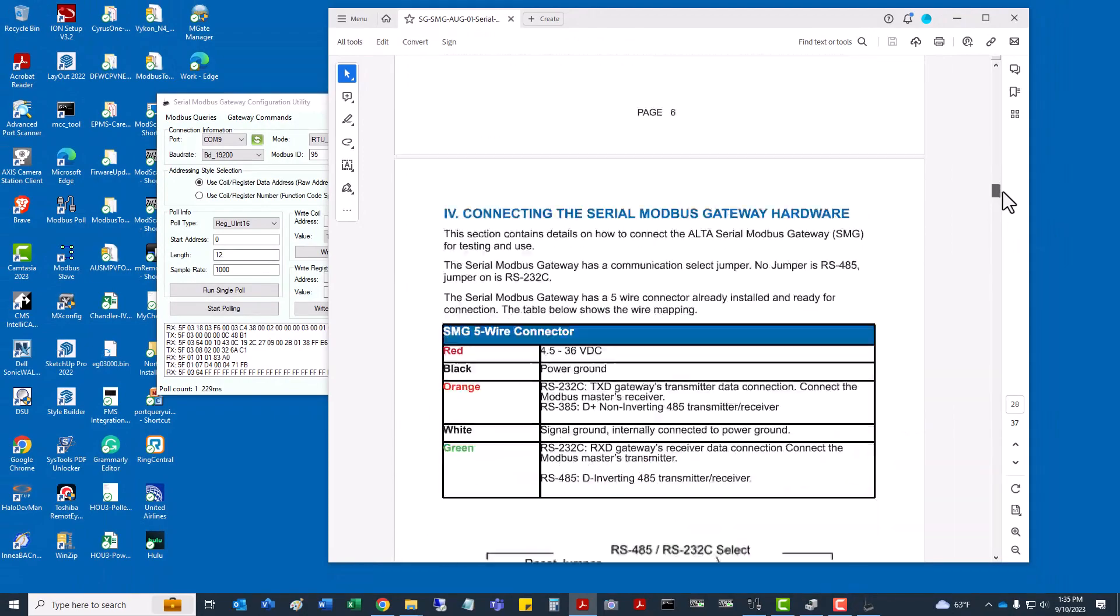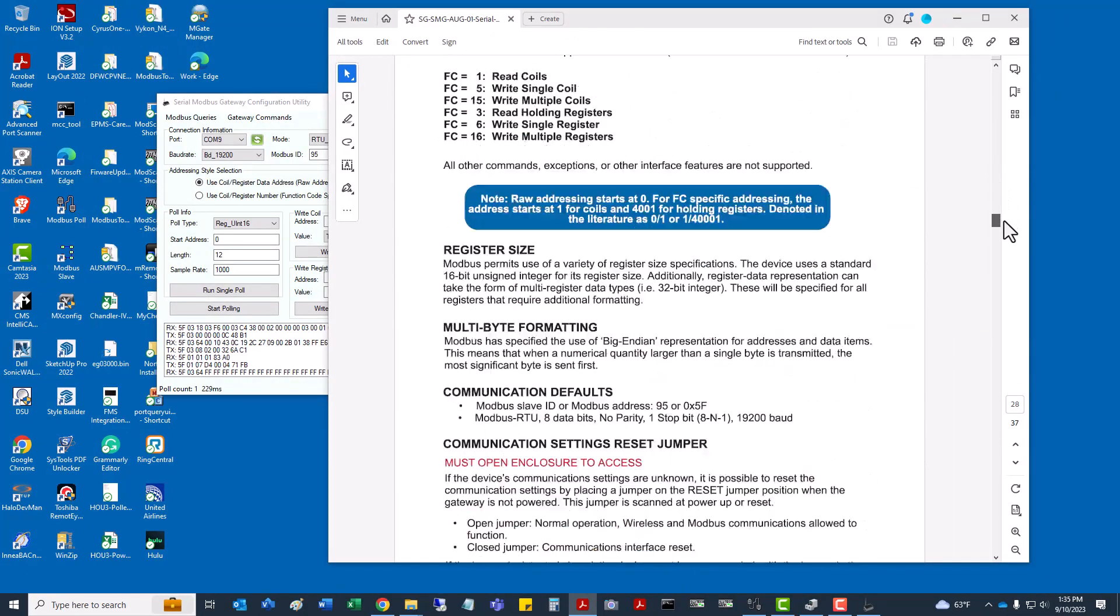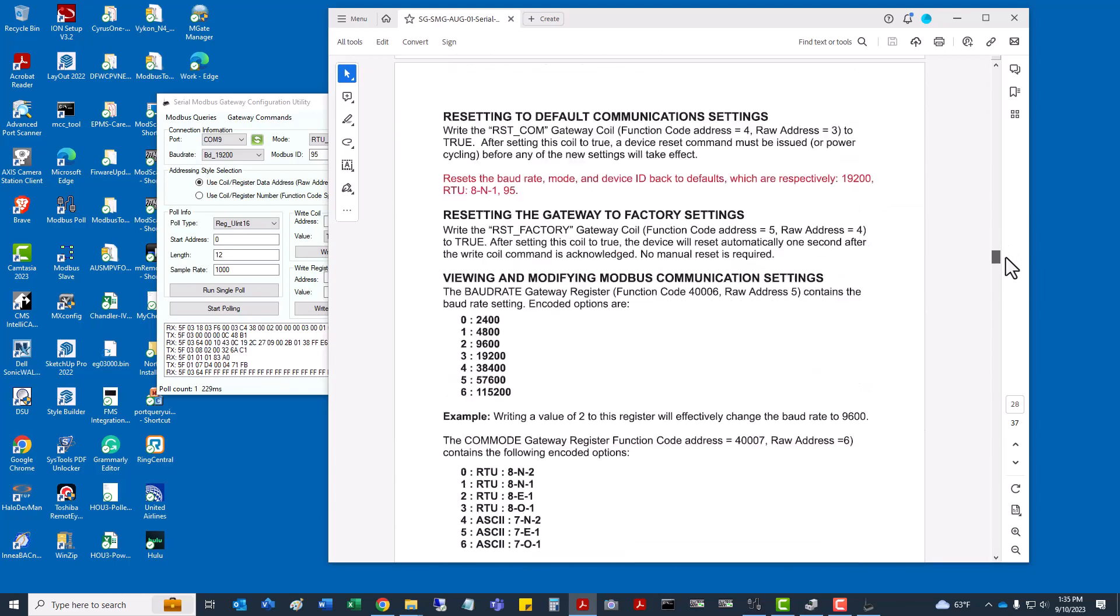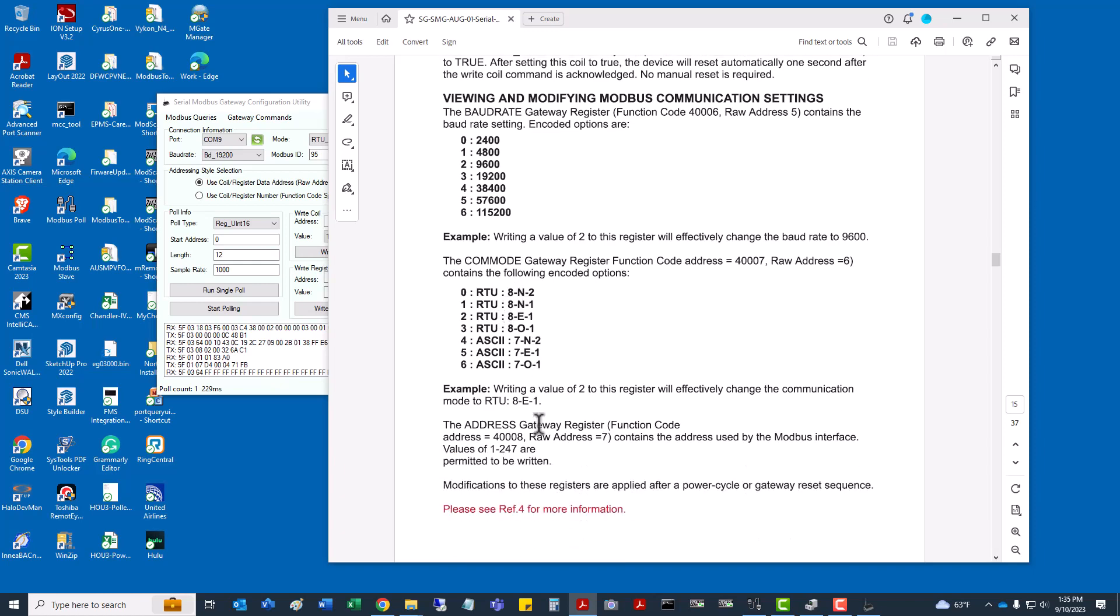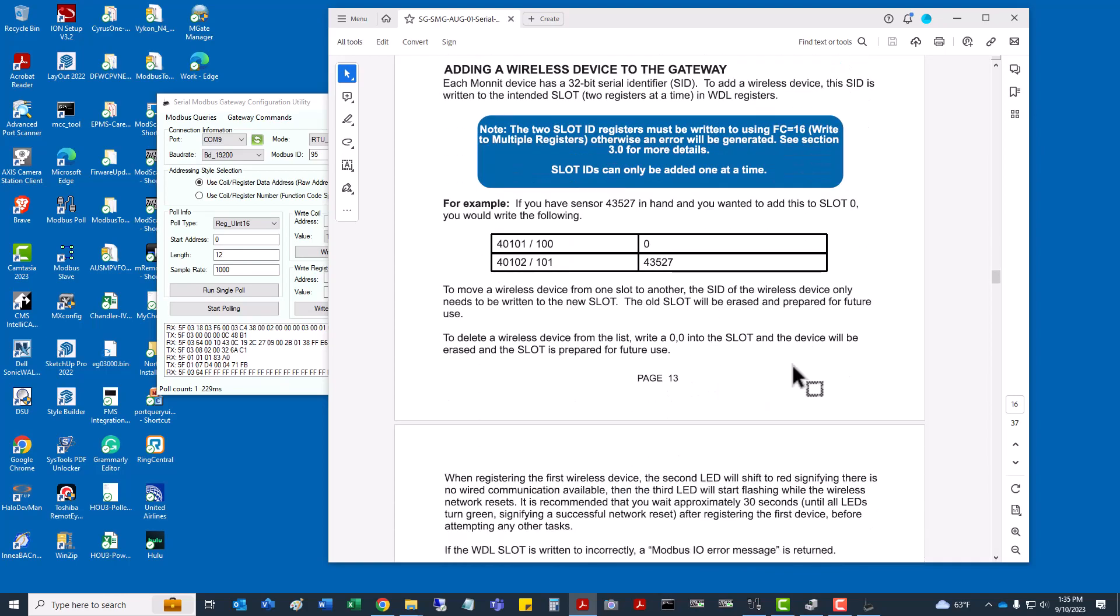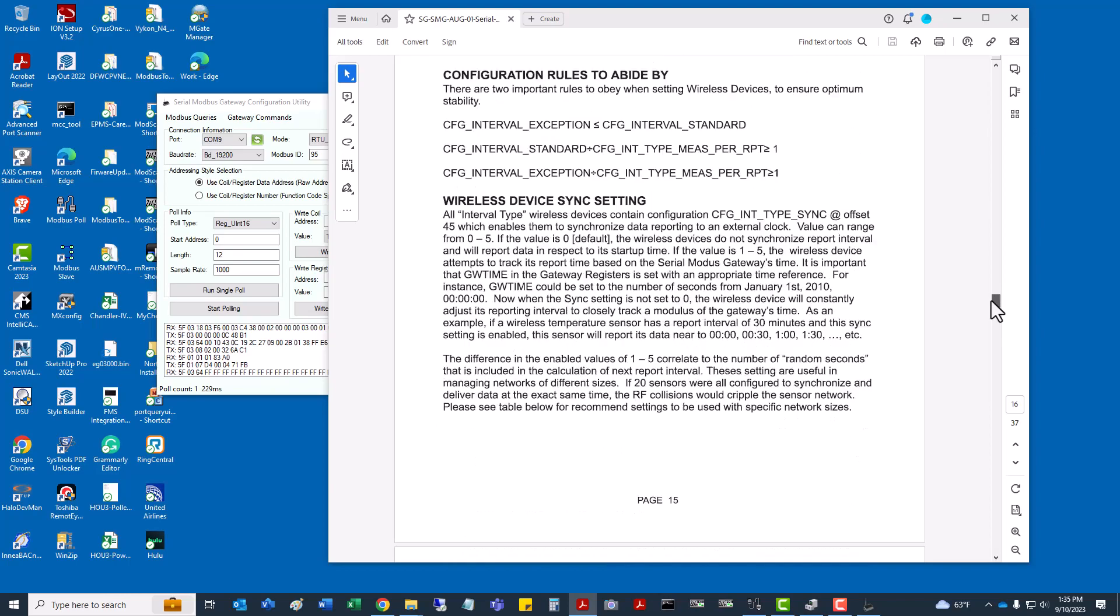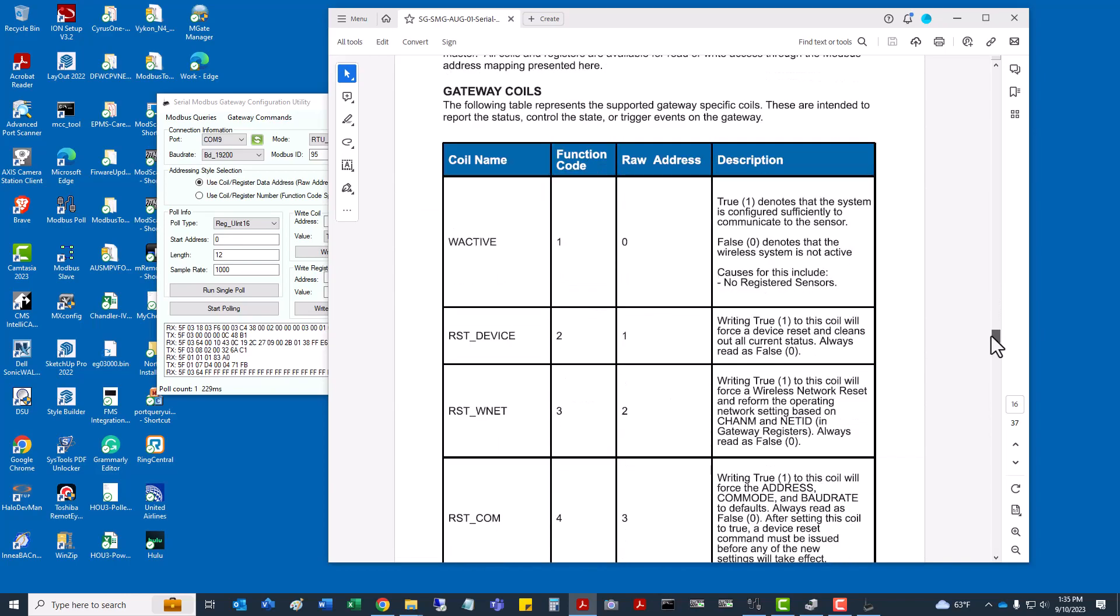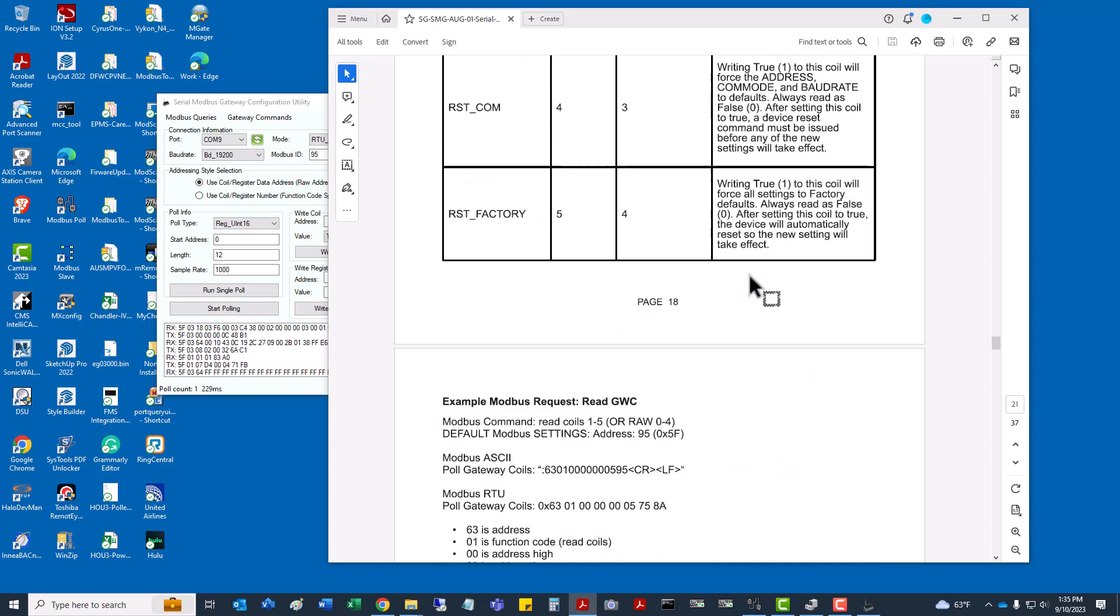One of the things I notice when you're in here, you can actually pull Gateway Registers. Based on these registers, I believe you can do some write commands if you're not using the utility, if you want to actually change those to different states, which they call out at the beginning of the user guide. If you didn't want to use the 19200 default baud speed or you wanted to change the other comm parameters going down through, you can do either RTU or ASCII. The default address on this unit is set to 95 from the factory.